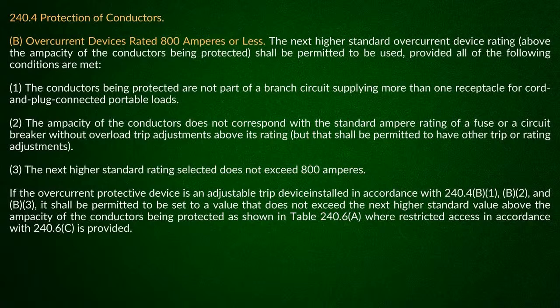There we go. Okay. When you look at 240.4(B), it says up at the front, the next higher standard overcurrent device rating above the ampacity of the conductors being protected shall be permitted to be used. What they're telling you here is you can protect the load or you can protect the conductors. Now, if he says I'm going to protect the load, then he's sizing the equipment grounding conductor based on what? A 600 amp.